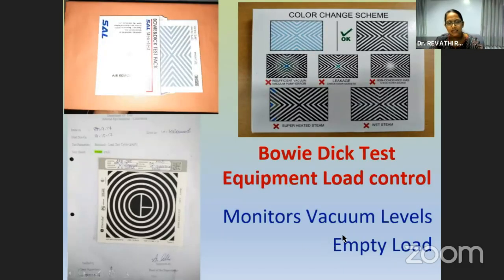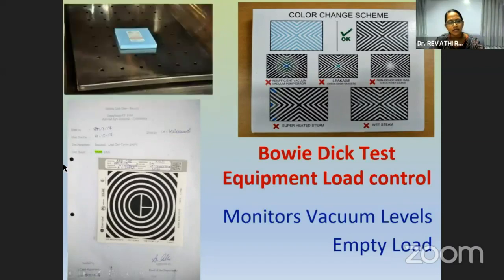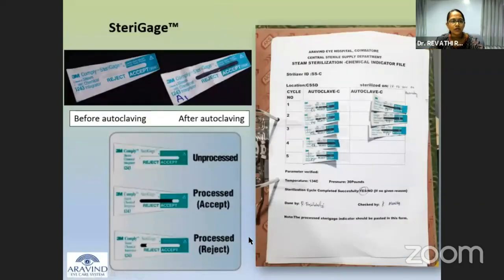The Bowie-Dick class 2 indicator gives us a clear idea, for an empty load, where the pack is kept in the top of the load. The pattern change according to the standard tells us that the autoclave machine's vacuum function has been functioning well. It has to be documented once a week. A Bowie-Dick definitely has to be put in for an autoclave.